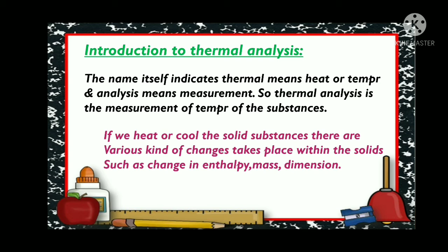If we heat or cool this substance, there are four kinds of changes. Either it may be thermal change, weight change or dimensional change, or gas is evolved under the application of cooling or heating. If a thermal change takes place within the substance, two kinds of techniques are used to determine it. First is DSC, differential scanning calorimetry, and DTA, differential thermal analysis. If a weight change takes place, then the TGA technique is generally employed, that is thermogravimetric analysis. If a dimensional change such as length or volume change takes place, then TMA, that is thermomechanical analysis, is used. If gas is evolved under the application of heat, then EGA is used. EGA means evolved gas analysis.